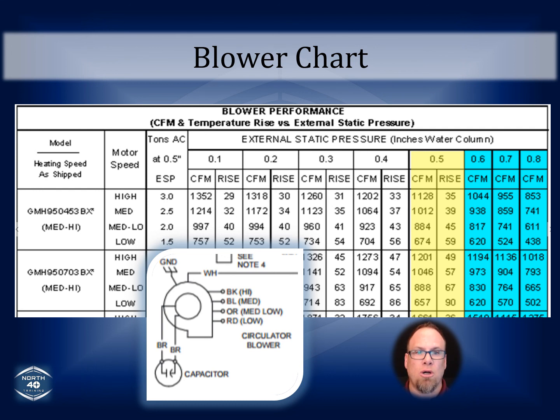It takes the cool away from your coil too quickly, so you don't get good dehumidification, you don't get a good air temperature drop across that coil. So instead of lowering the blower speed like you should to the correct CFM value, you go out and you add refrigerant to the system outside. And when you add refrigerant, it fills that coil a little bit more and creates a little bit better temp drop. Never perfect, but it gets it to the point where it's working fairly well.